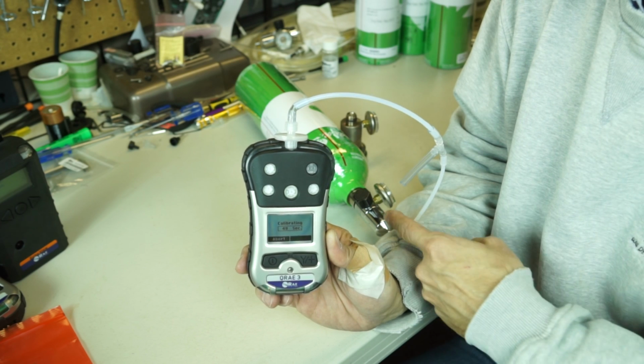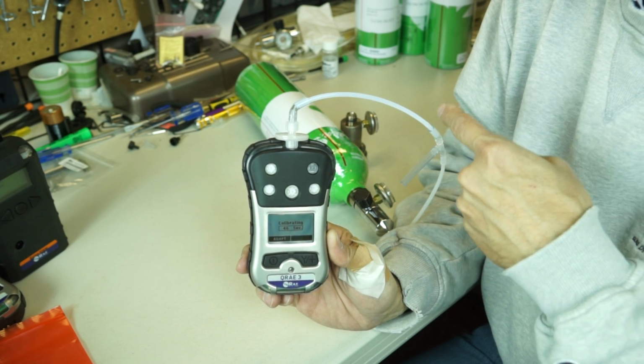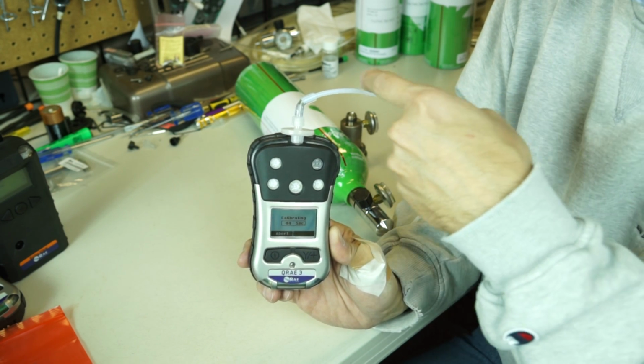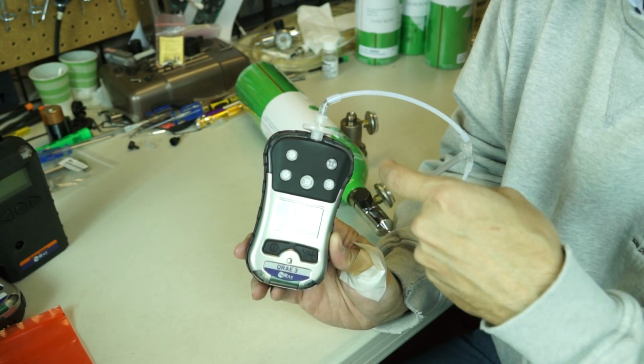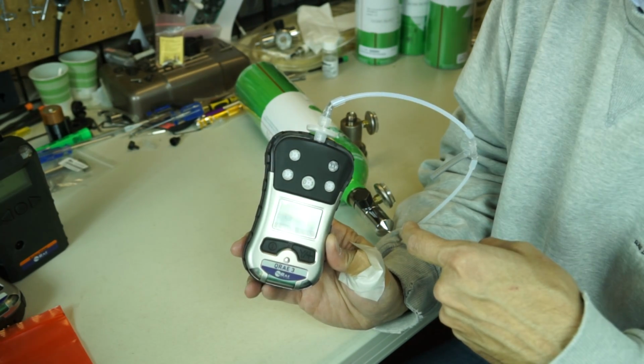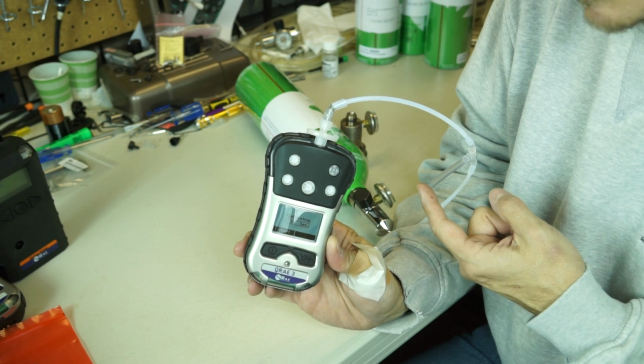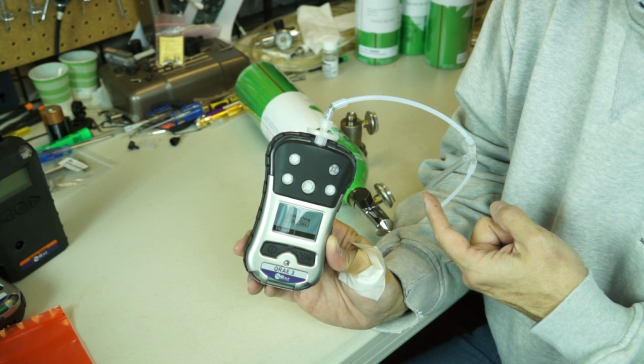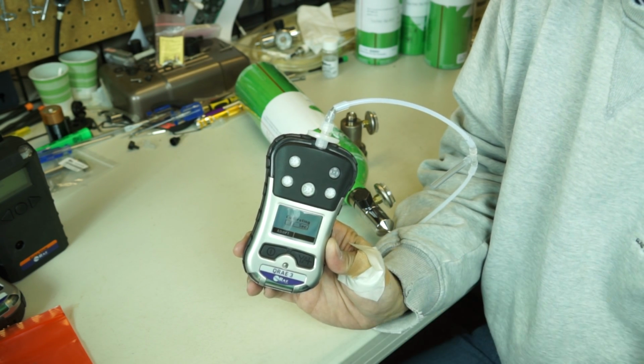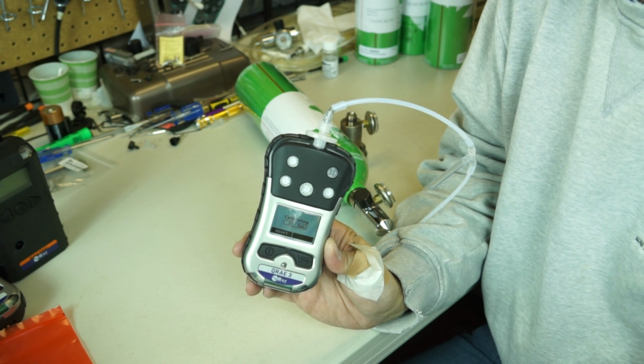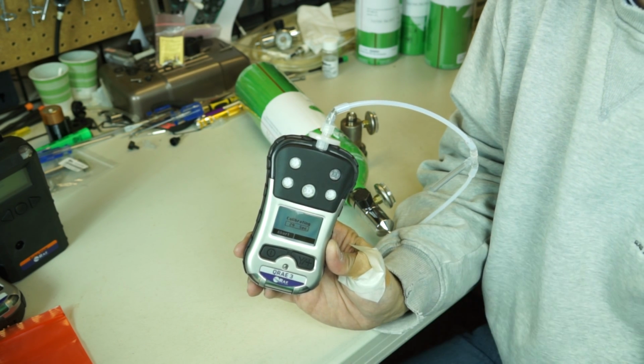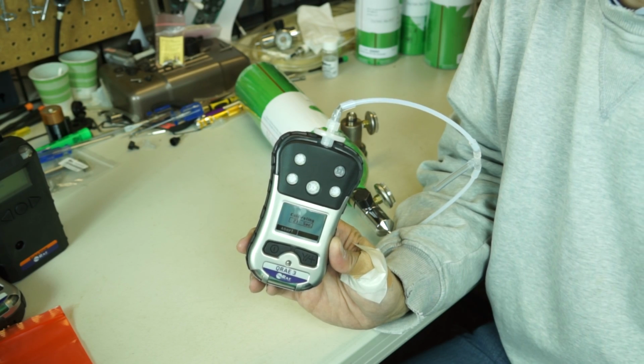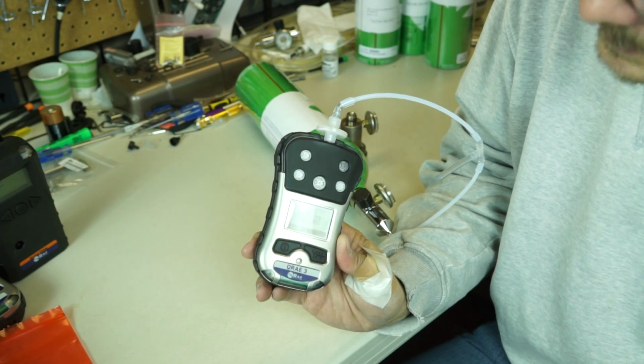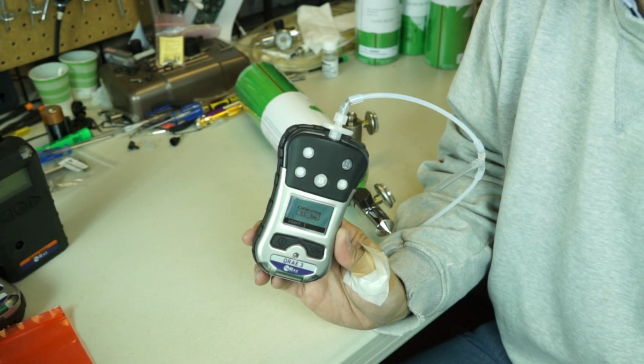So what's happening here, the gas is coming out, in this case a 1 liter per minute regulator. It's going right up into the instrument. And any excess is coming out the third leg. So what this means is the instrument is basically pulling at its own rate. The pump is pulling at its own rate. Any excess is coming out the third. Now, we've always talked about T's in the past. So Rae Systems, I'm happy that they've actually included the T for you.